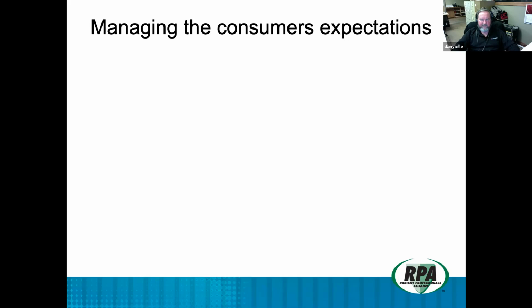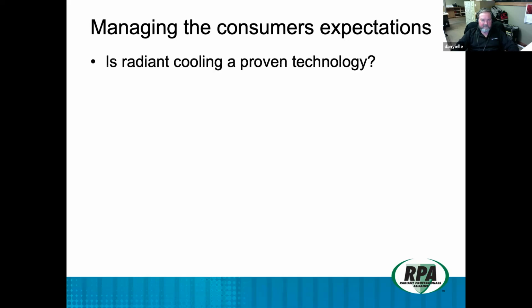There's a whole lot of different options that you can use to pick up the balance, but you absolutely cannot do anything with the latent load. You need either a dehumidification system or a cold coil that you can extract the moisture out of the air with, and control the relative humidity within that space. But good question, valid point, thank you.